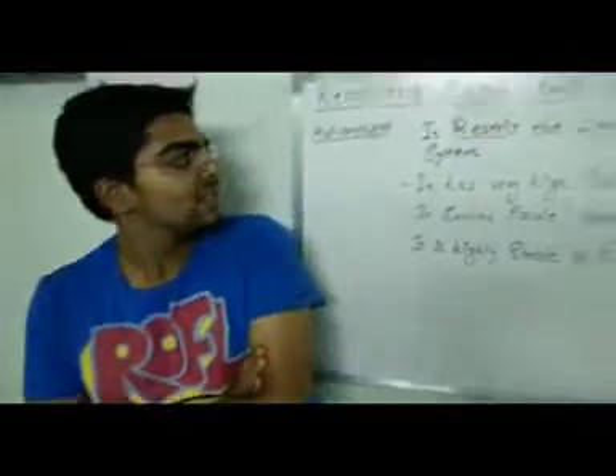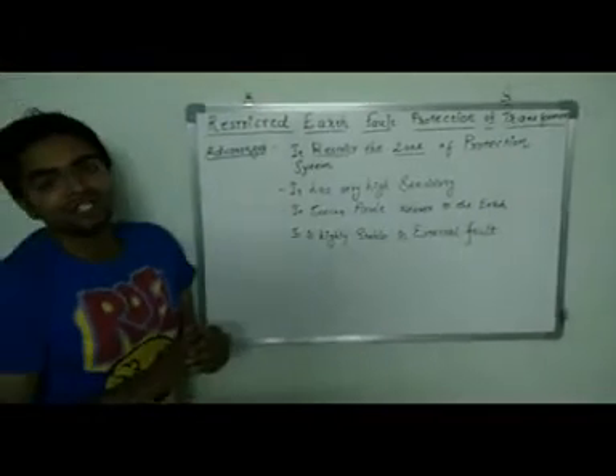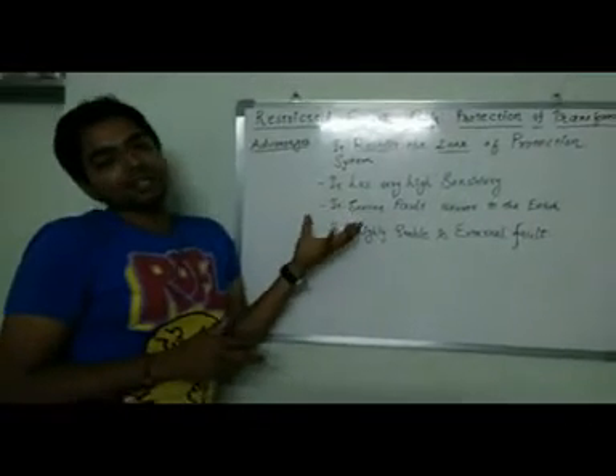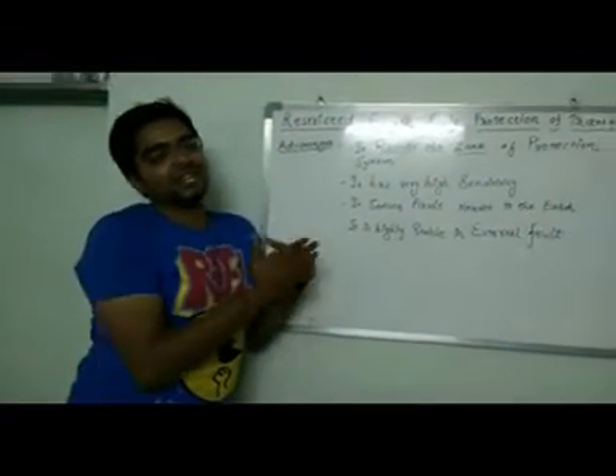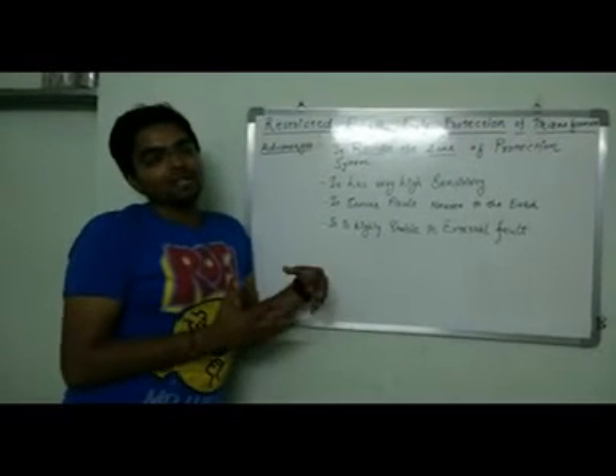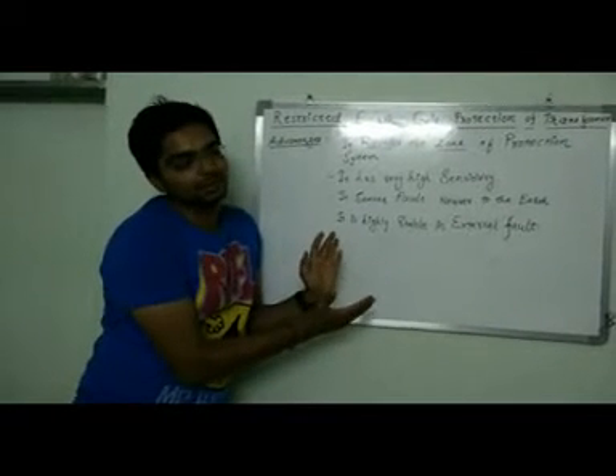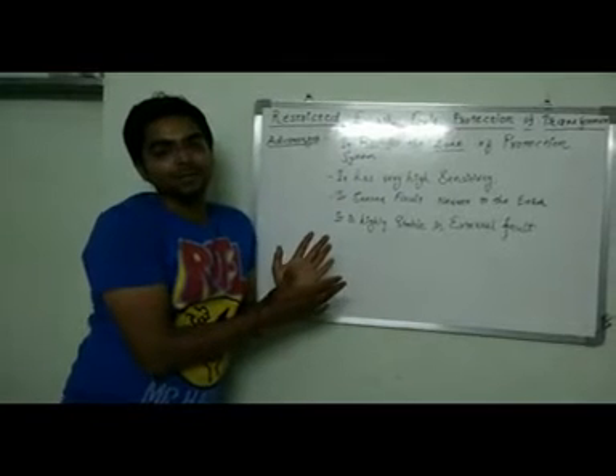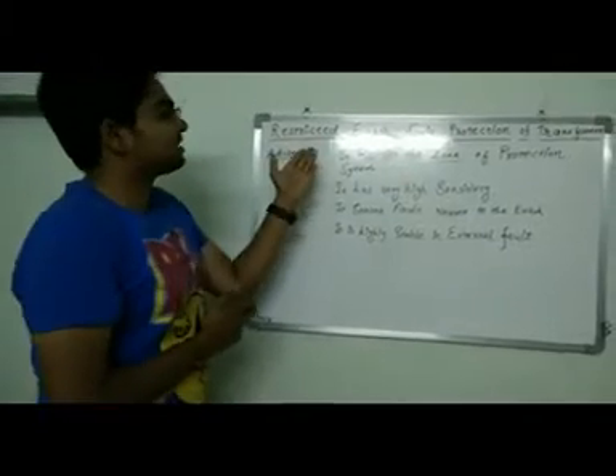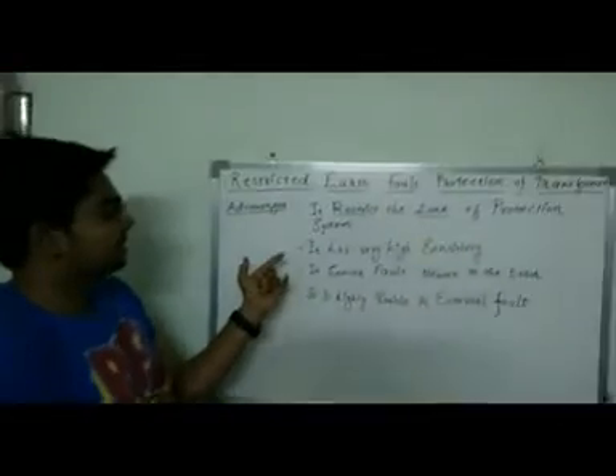And the main advantage of this project is that it restricts the zone of the protection. Let's take an example to understand this point. If it is a 100-kilometer transmission line, it is very hard for us to detect the fault. But if we restrict the zone, if the zone becomes very small, it is very easy for us to find the fault. That's why we say it is restricted fault protection. So it is very highly sensitive. It senses the fault near to the earth.